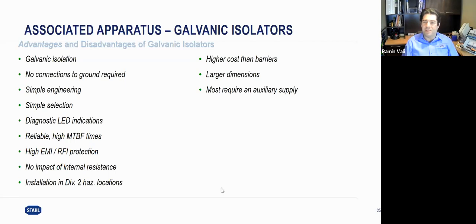Because they have more electronics, sometimes they have microcontrollers inside, and diagnostic LEDs. Sometimes you have more diagnostic features, like a relay that we can connect to the PLC to create an alarm in case of a fault in a loop. They are very reliable products. They have very good performance against EMI, electromagnetic interference, or RFI. And they don't need to have an external ground connected to them. Installation in Division 2 is permitted, and they can be an associated apparatus to connect Division 1 or Zone 0 equipment to the safe area.